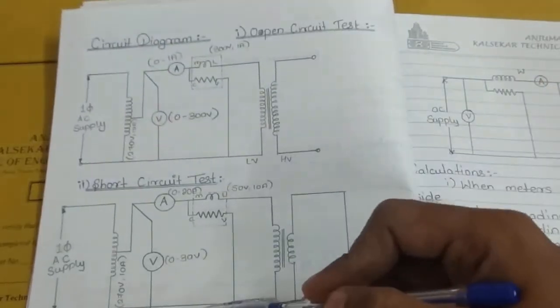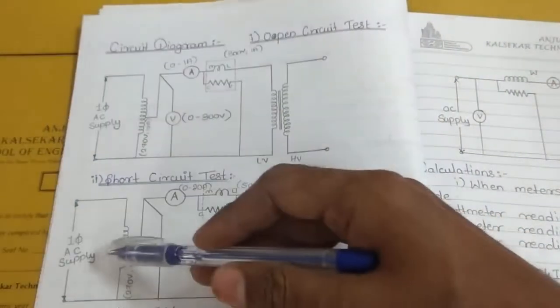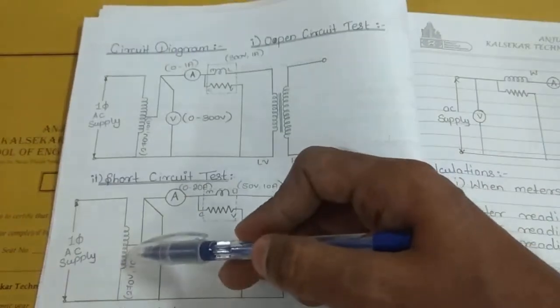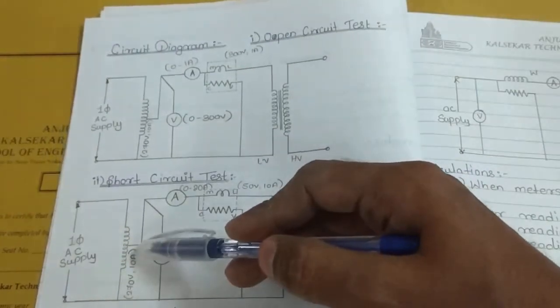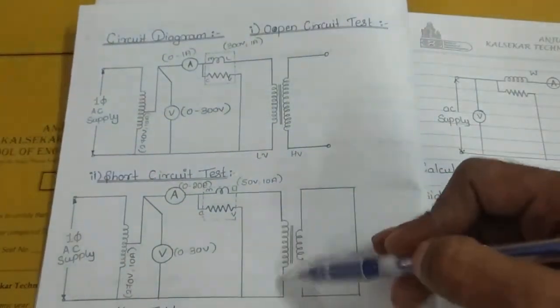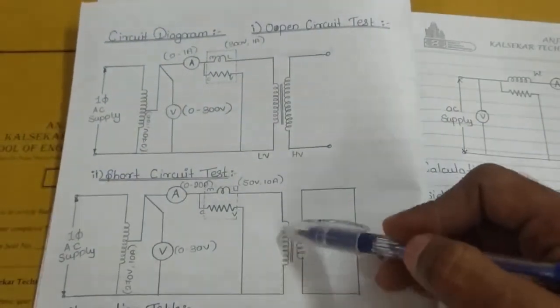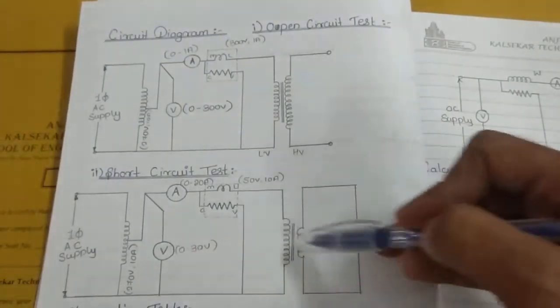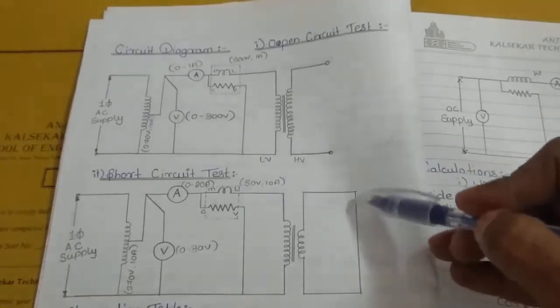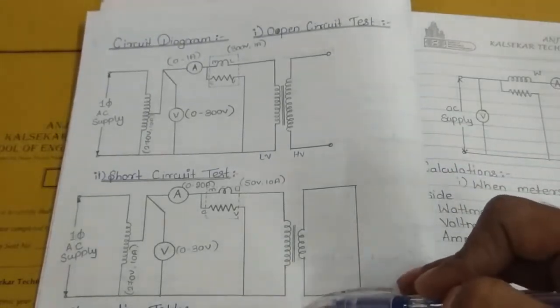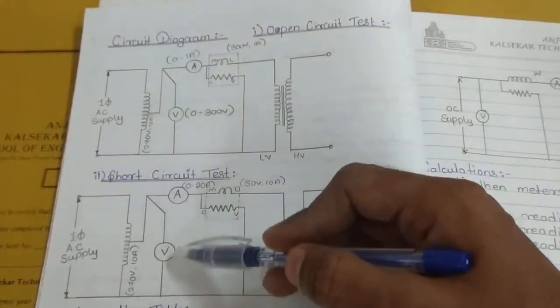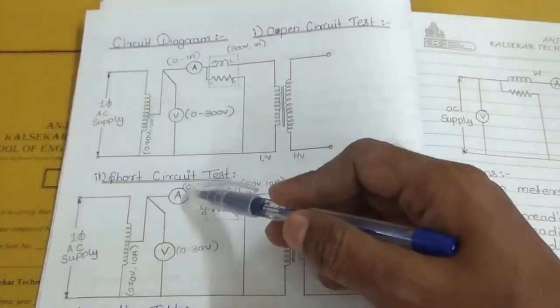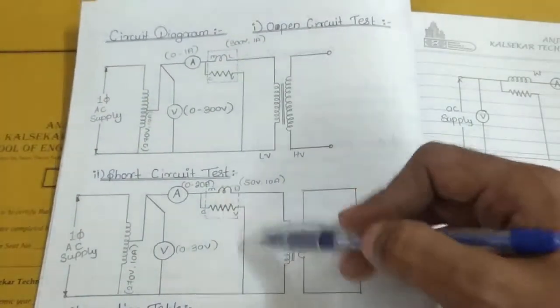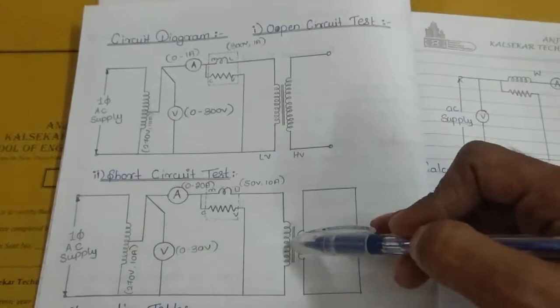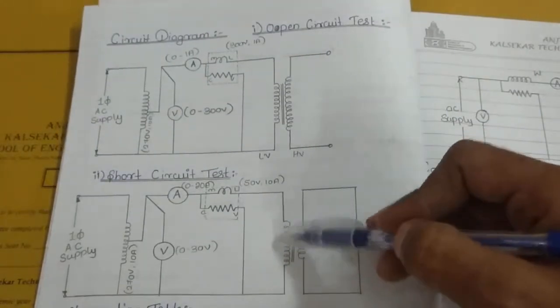And for the short circuit test, we will connect the supply to the variac input and the output of the variac will be connected to the HV side of the transformer, and the LV side of the transformer is short circuited. And in the same way, we will connect the voltmeter in parallel, the ammeter in series and the wattmeter in series and parallel to the HV side of the transformer.